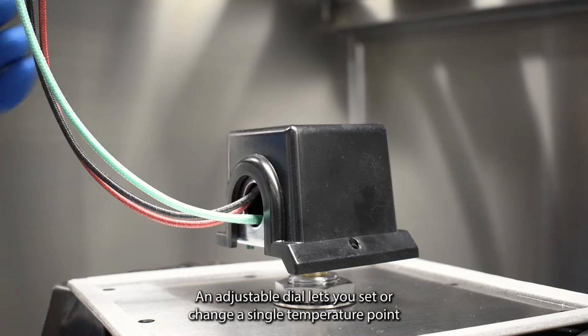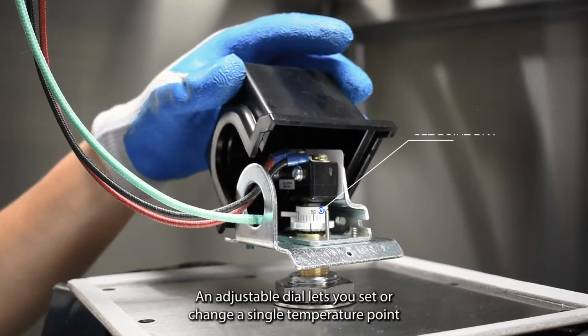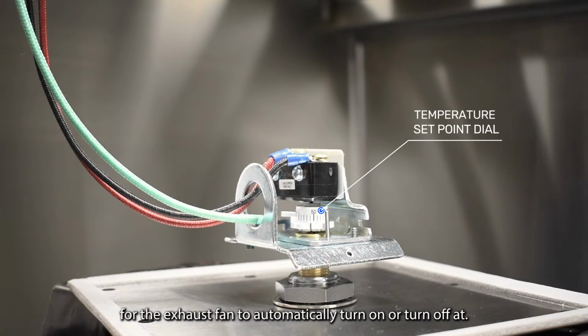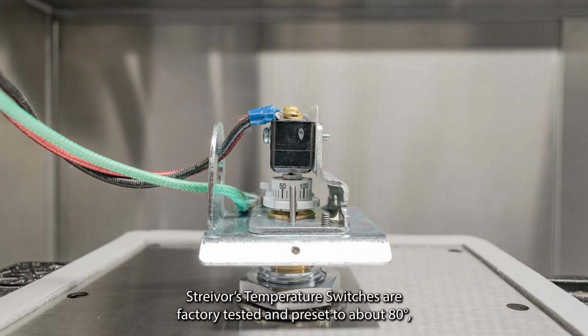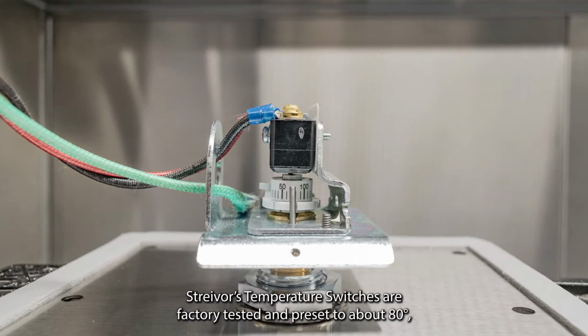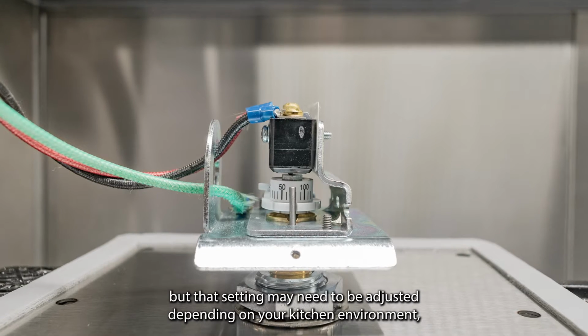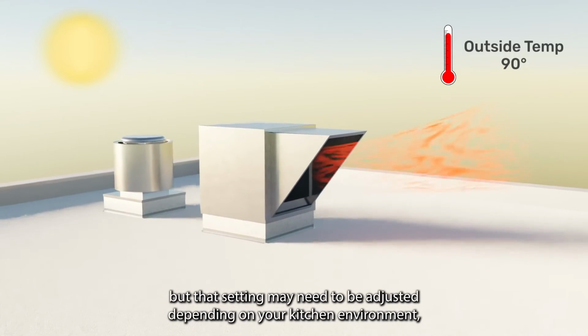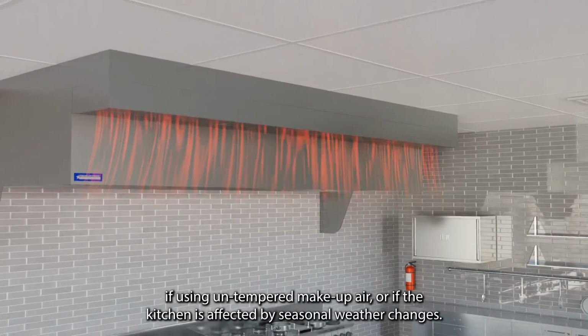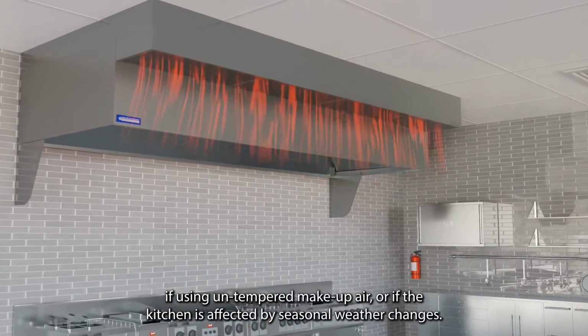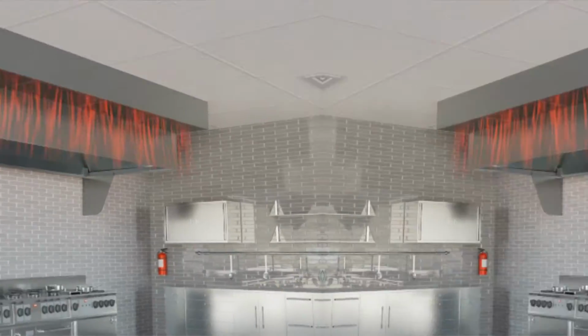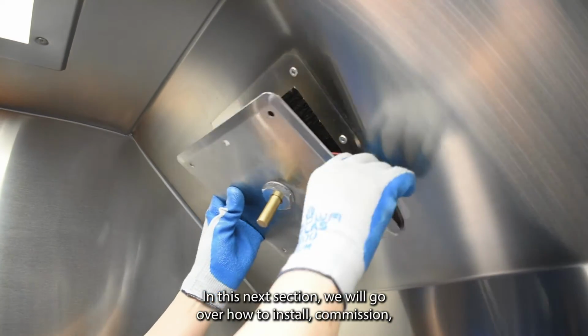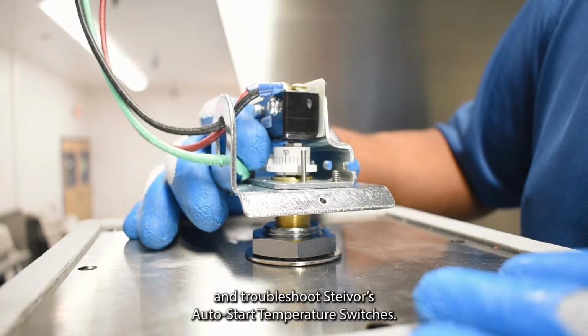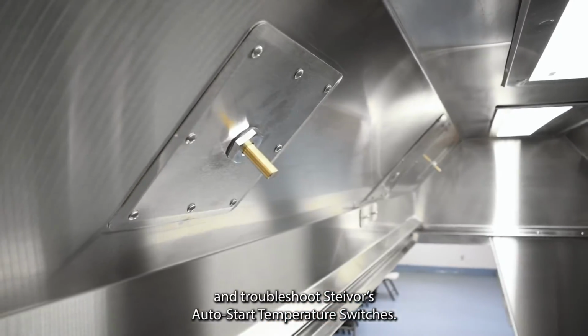An adjustable dial lets you set or change a single temperature point for the exhaust fan to automatically turn on or off at. Streivor's temperature switches are factory tested and preset to about 80 degrees, but that setting may need to be adjusted depending on your kitchen environment, if using untempered makeup air, or if the kitchen is affected by seasonal weather changes.